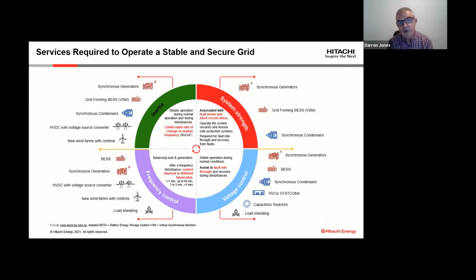So voltage is controlled and managed by making sure we have the right level of system strength, which is effectively a measure of the impedance of the network. The network is designed to have a certain impedance to make sure voltage is managed. Voltage control is typically more difficult on long overhead rural networks, where we have long feeders, and voltage will tend to drop per unit length of the feeder. So there's great emphasis on managing and controlling voltages.